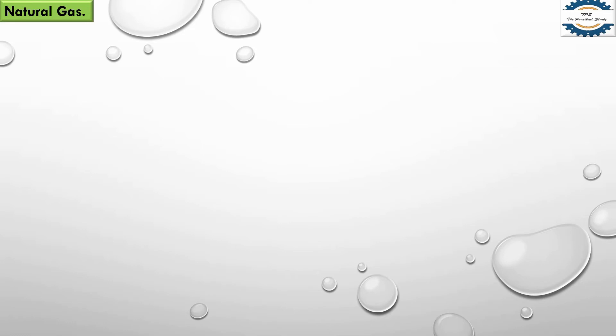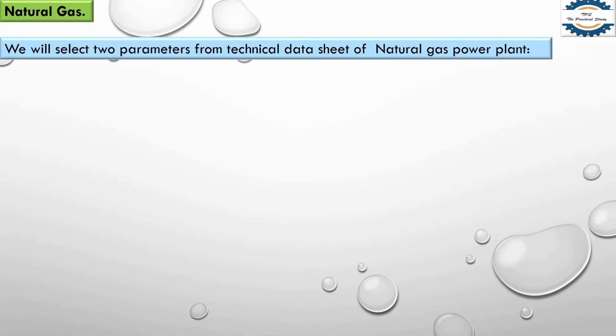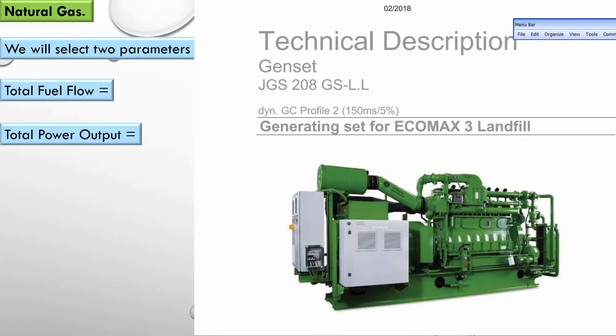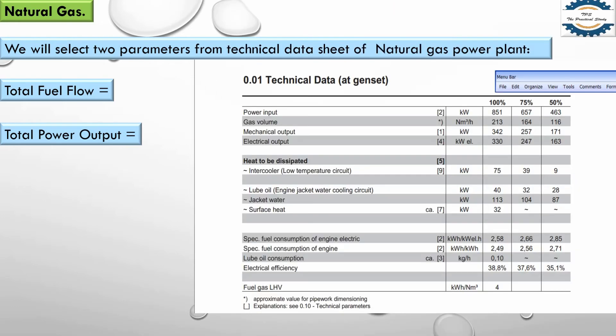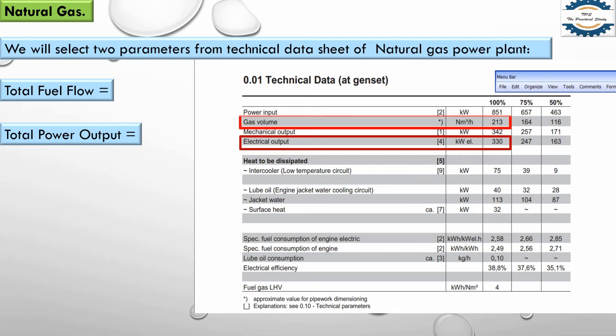Let's move on to natural gas. To calculate the specific fuel consumption and heat rate for a natural gas power plant, we selected two parameters from the technical data sheet of a Jenbacher gas generator, model JGS 208 GS-L.L. The first parameter is electric output: 330 kilowatt at full load. The second parameter is gas volume: 213 cubic meters per hour.